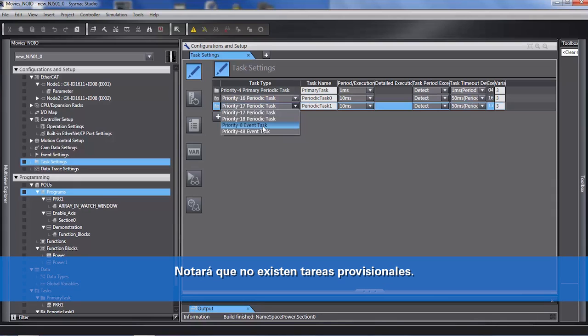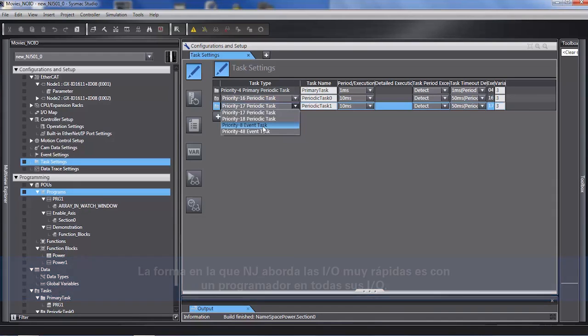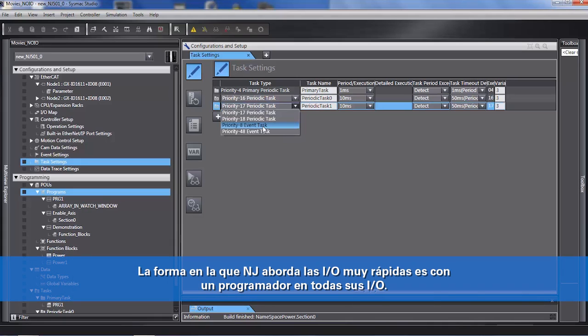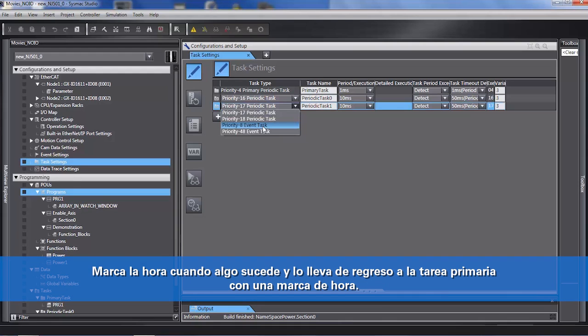You'll notice there are no interrupt tasks. The way the NJ deals with very fast IO is it has a time clock in all of its IO. It timestamps when something happens and brings it back to the primary task with a timestamp.